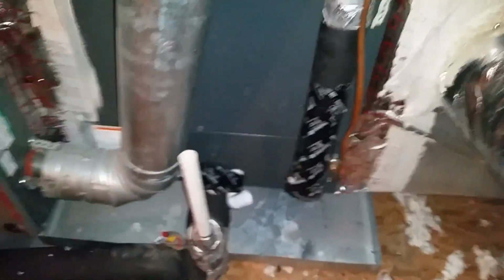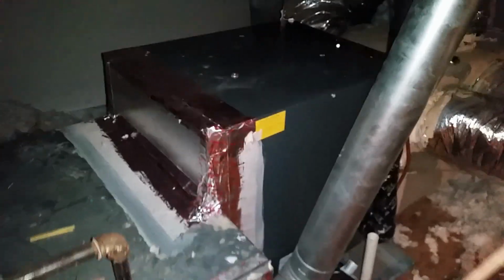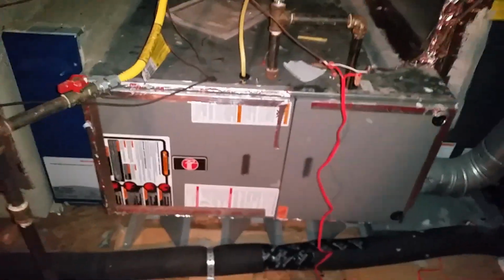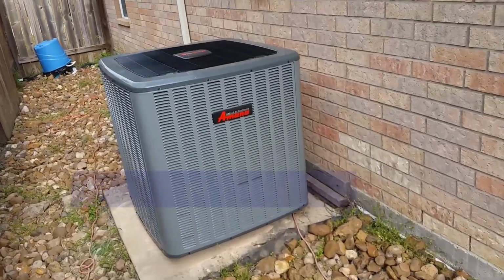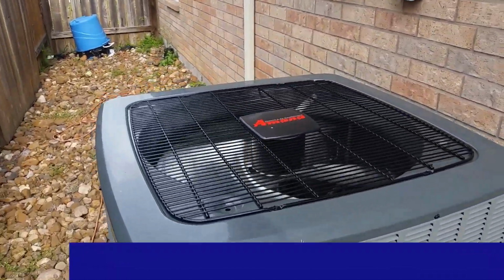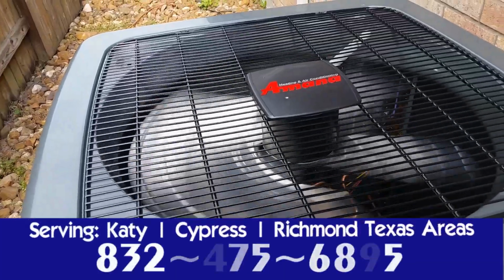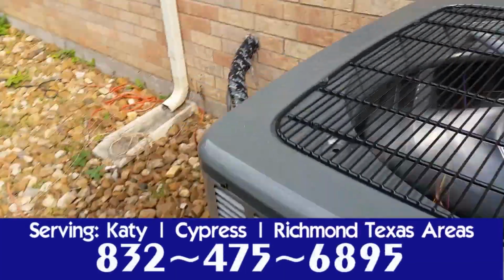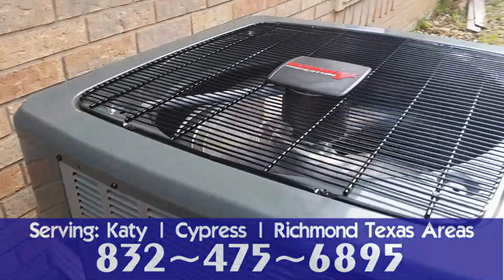So the install turned out really well. It's really pretty typical. I mean, I do this quite often, and so really nothing out of the ordinary with this install. Obviously, I could have fixed this another way. I could have just repaired the coil only. That's always an option, but given the R22 problem, if the system ever springs another leak, then it's always got that R22 stigma attached to it, because R22 is being phased out and the price is only going to go up.